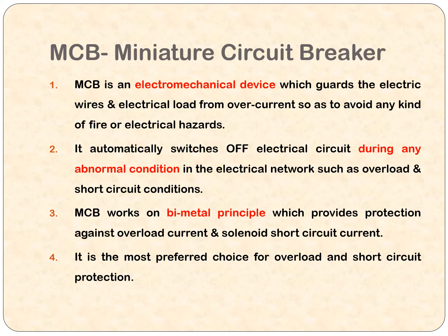In day-to-day life, if some abnormality, that is overload, happens, you will hear a sound from the MCB as it automatically switches off. So how is it working? It will automatically switch off and it will never be turned on automatically. You need to go and manually turn it on. You do this a lot of times. Instead of changing the fuse, you are making use of an MCB in the home.